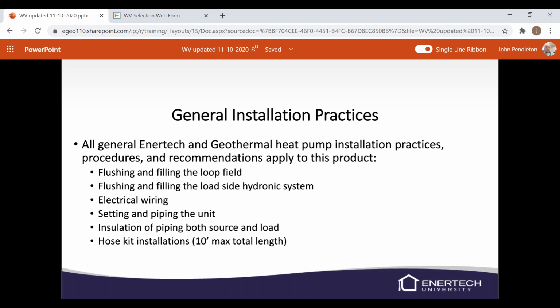So general installation practices, all Enertech and geothermal heat pump installation practices, procedures, and recommendations apply to this unit as well. So we still have to flush, we have to fill and flush the loop field. There's no difference there. We still have to fill and flush the load side. There's still electrical wiring, the same. Setting and piping the unit, not a whole lot of difference.